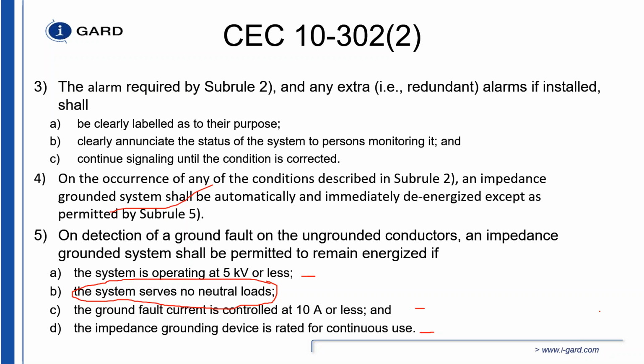So obviously, if you saw my previous webinars, having a system that's 5 kV or less and less than 10 amps is not only a good, effective arc flash mitigation system, it is very safe to do that, but you have to monitor the integrity of the resistor. You're not necessarily going to have a distributed neutral on every system.